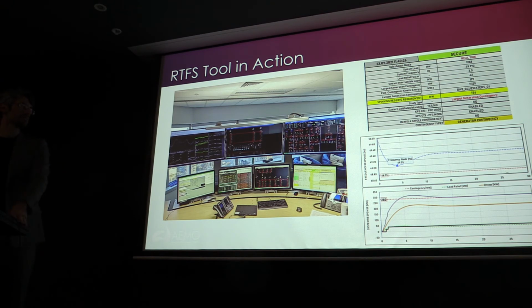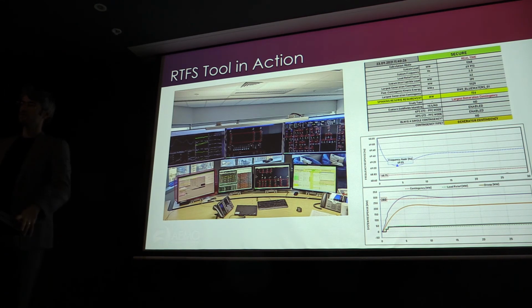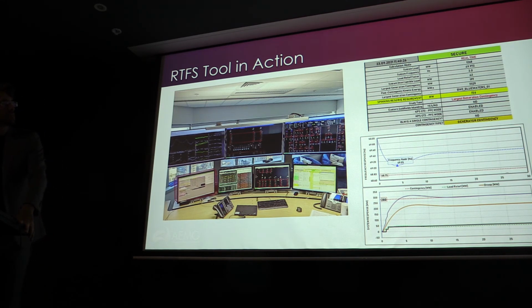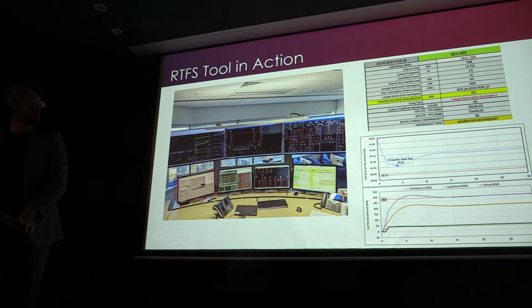And the tool in operation in the AMOS control room. This is our tool sitting there, and that's the main page. On the top, you can see a green color means secure. Why? Because that's the trace for that time. We had Blue Waters as the largest contingency at the time, at around 200 megawatts. That's the frequency trace. The frequency nadir predicted was around 49.05, indicating the system is hypothetically secure, and everything is fine in terms of RoCoF and frequency nadir.